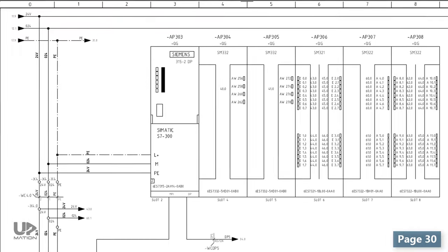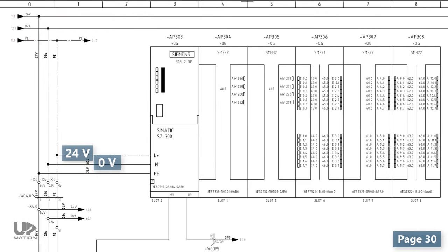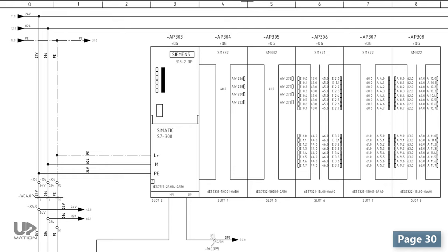The 24V, 0V, and the earth are respectively connected to L+, M, and PE terminals on the PLC CPU. Same as always, if we are designing a wiring diagram and we are not sure about the connections of our device we have to take a look at its datasheet or manual. For example, here we should see the PLC datasheet to figure out where we should exactly connect the wires.